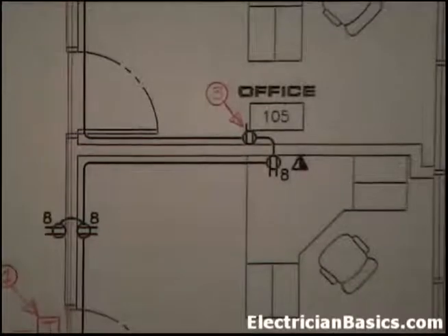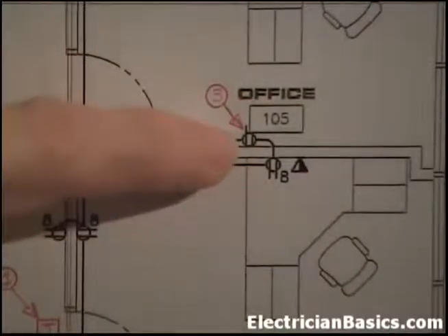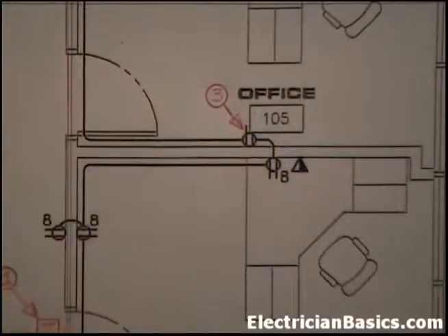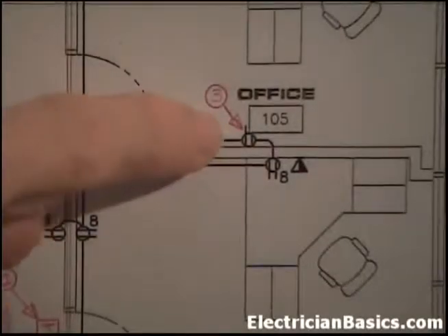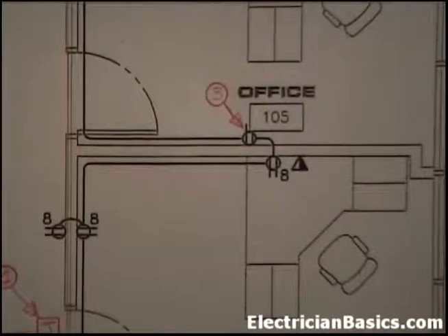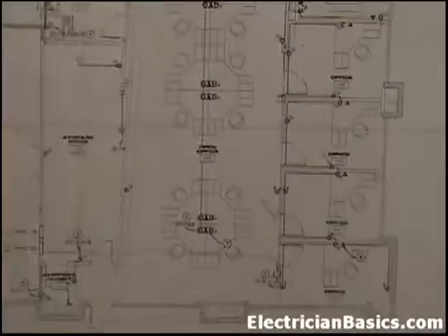The red line diagram, we're showing what has been built. So, and I should have pointed this out earlier on the power print. That would have been a good time when we were on that page the first time to show this, but I didn't really catch it till I was redlining. But the thing is, when you build this, you got to determine, is this circuit 10 or circuit 8? So let's find a good way to do that if you don't have somebody like the electrical engineer or the architect or somebody like that telling you.